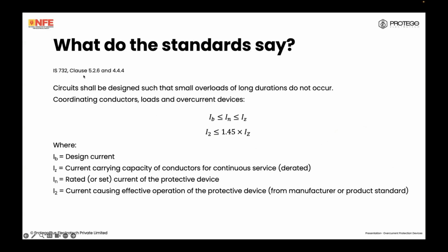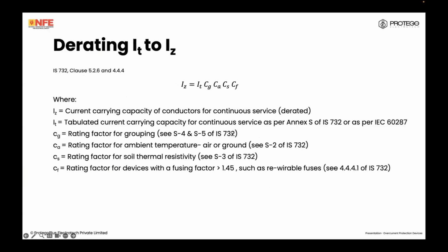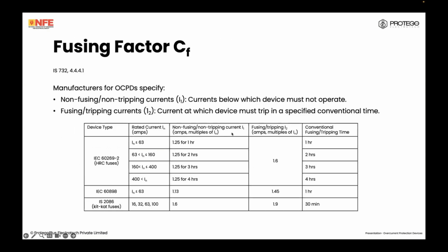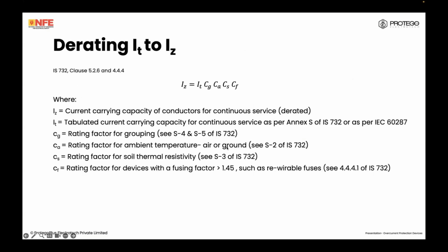IS 732 clause 5.2.6 and clause 4.4.4 specify that I2 shall be lesser than or equal to 1.45 times IZ, which means the current causing effective operation, the conventional tripping current or fusing current, shall be lesser than or equal to 1.45 times IZ. If the circuit is running at full operation, we need the IZ to be equal to the IN. This is the worst case scenario. A 1.45 fusing factor is all that is acceptable as per this. However, for an HRC fuse, this is 1.6. So we need to derate the cable. That's just something to keep in mind.